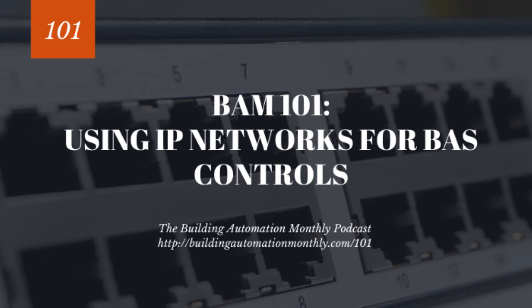But that's not a standard tech tool, and I can't see any tech really dragging an oscilloscope around in the field. It's not really possible. So there's the testing issue - this doesn't exist. Until you turn it on, plug it into your software and go, 'oh, I'm only getting half the devices.' Now you're in for a trek to go figure it out and find it.